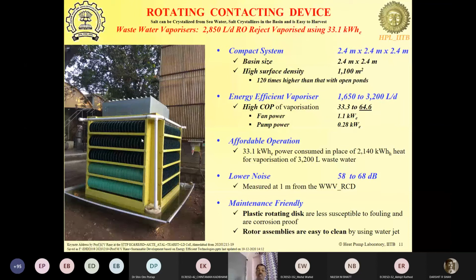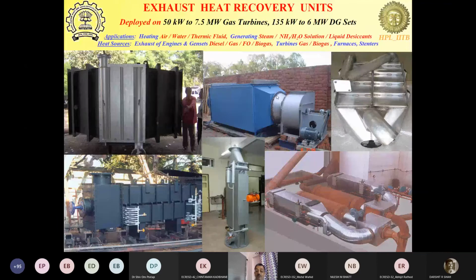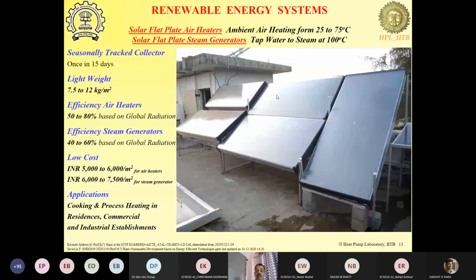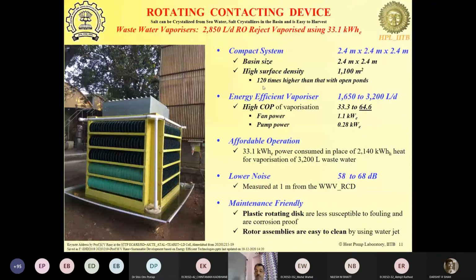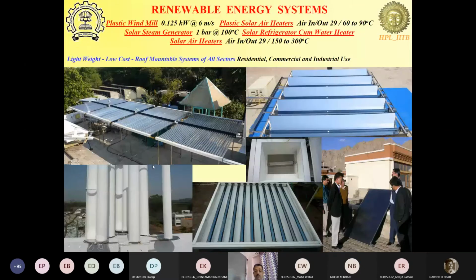The main thing here is the very high surface area that we provide in a very compact space. If you compare the surface area offered by all the discs provided here, which get wet, as compared to the pool area, which is around 2.4 by 2.5 meters, somewhere between 6 to 6.25 square meters, and the wet surface area provided by all the discs on all four sides is around 1100 square meters. So the ratio of the pond area to this is almost 120. So if you're looking at solar ponds to vaporize wastewater or seawater, this can do a significantly higher amount because of the 120 times increased surface area in this particular case. And the noise is also low. We have deployed these as cooling towers also. We'll see some of the slides later.